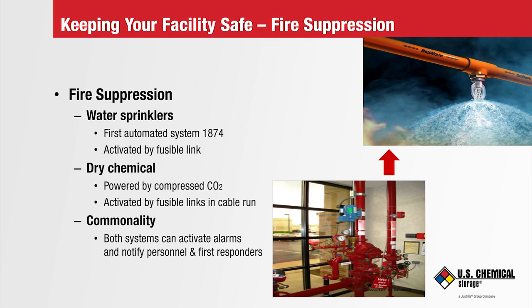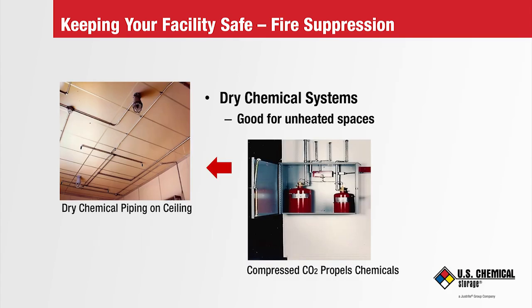Or there's a dry type of water sprinkler that has no water in the piping prior to discharge, just air. When a fusible link releases, the air comes out first and then the water will be released from a heated nearby facility into the sprinkler piping. And you can see that in that lower left-hand photo that was up.